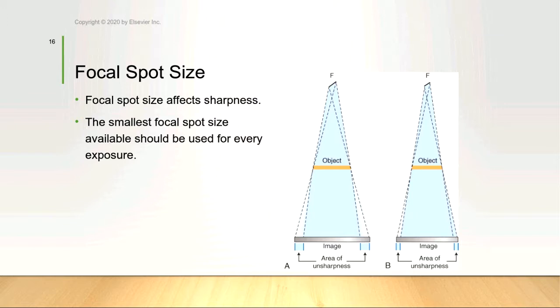Typically, the rule of thumb is for extremity work, you use small focal spot because they're not having to hold their breath or anything like that. And for trunk work like chest, abdomen, anything that falls in those areas, we tend to use large focal spot because not that we're not concerned with the resolution, but there's so much anatomy in there that resolution is not your main factor of concern.